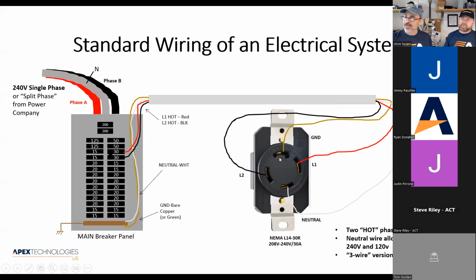The 4-wire has the 2 hots. So if a piece of load equipment needs 240 volts, it will just go between L1 and L2 and use those 2 wires. But sometimes it costs money to take 240 volts and bring it down to 5 volts DC. It's a whole lot cheaper if I can take 120 volts and turn it into 5 volts DC. So if my piece of equipment includes a neutral wire, then inside it I can go between either one of these phases and neutral and get 120 volts. So you'll see both 3-wire and 4-wire.